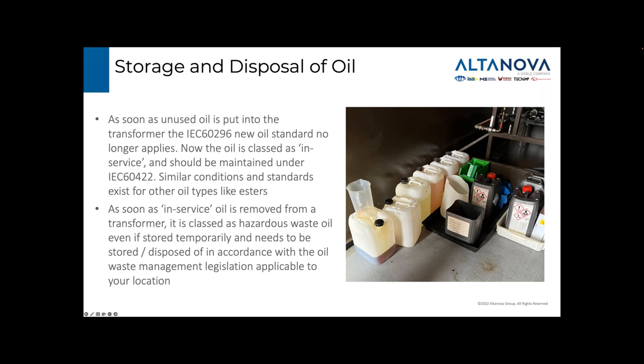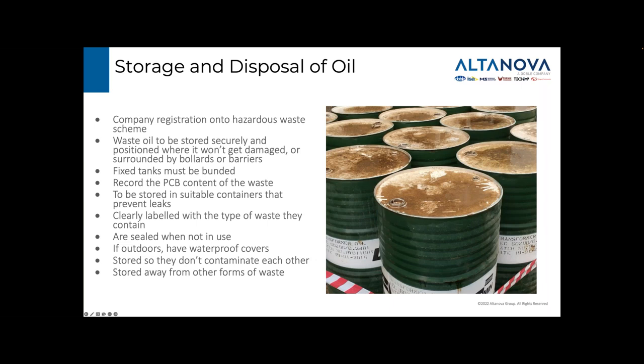Once the oil is in service and then becomes removed from the transformer for maintenance activities, it is now classified as a hazardous waste, even for temporary storage, and needs to be stored or disposed of in accordance with local oil legislation. Waste oil needs to be disposed of in a manner appropriate to your local legislation. This may mean you have to register onto a hazardous waste scheme, even for small volumes of oil. Larger volumes, for example, 3,000 litres per year, may even require specific site licences.